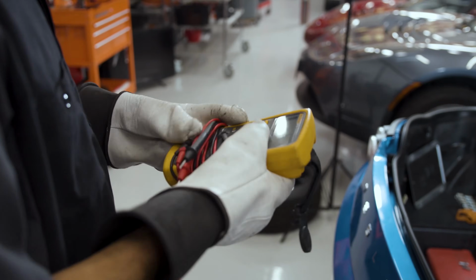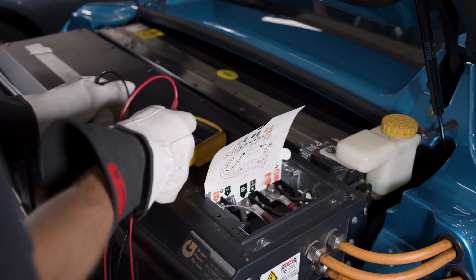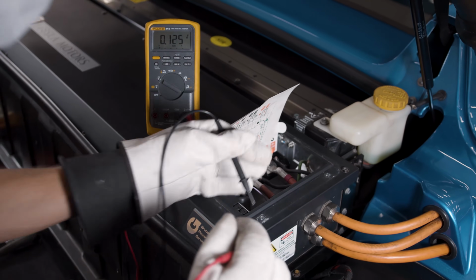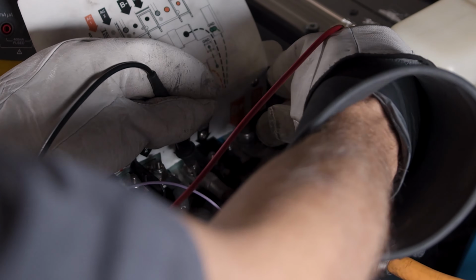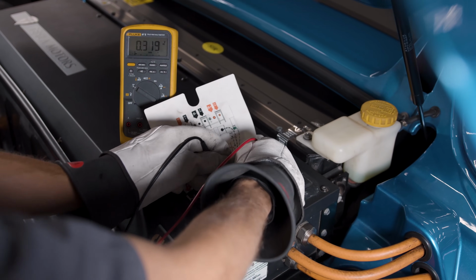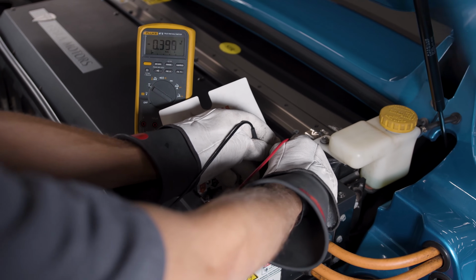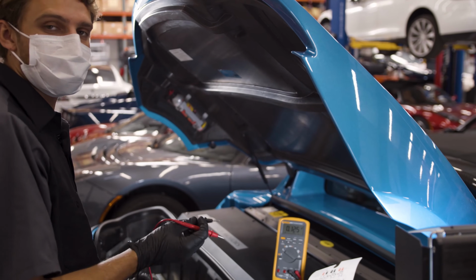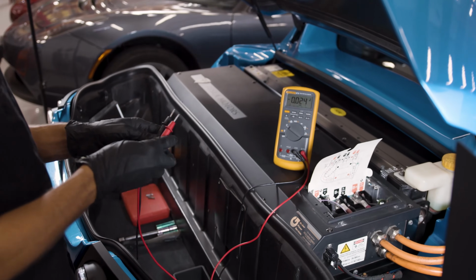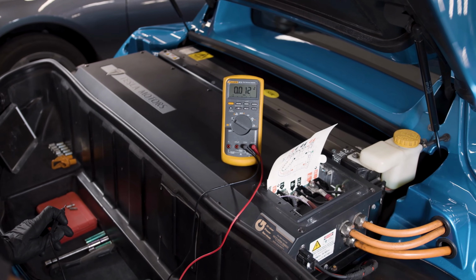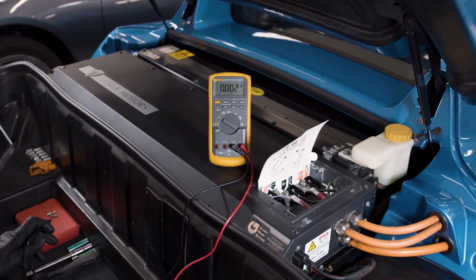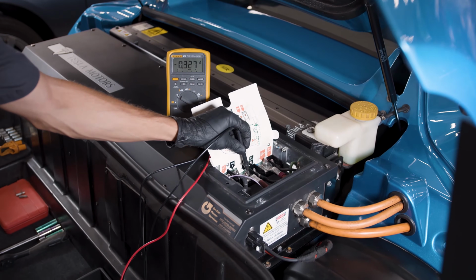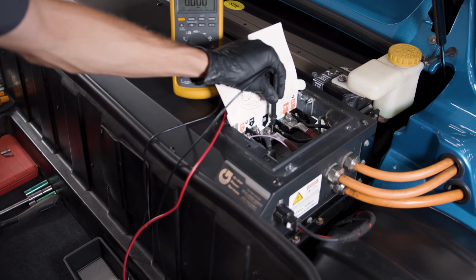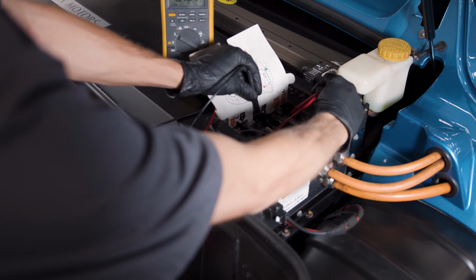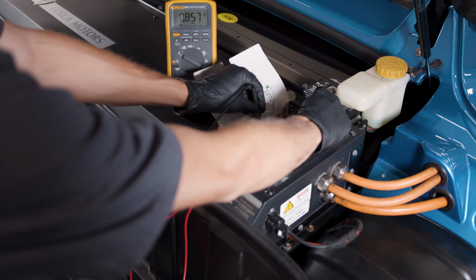Okay, time to glove up. Let's check to see if there's any voltage present. Battery negative, battery positive — that's okay. Battery negative, battery positive — that's okay. So what we just did was check to make sure there was no high voltage present on the high voltage bus coming from the battery. If there was, or if you see anything over 3 volts, do not touch it — you've still got voltage present and you don't want to get shocked. We measured between the battery negative and battery positive posts, and you can see we're well within the limits.